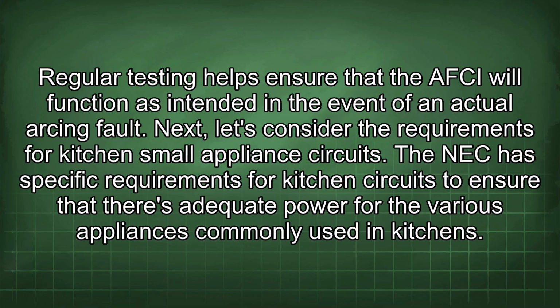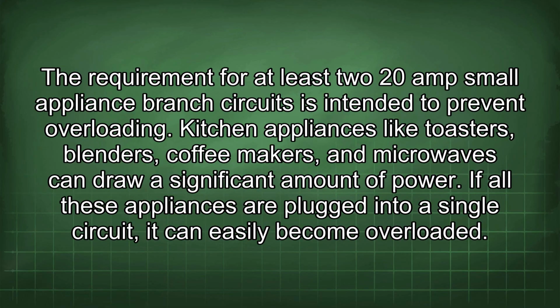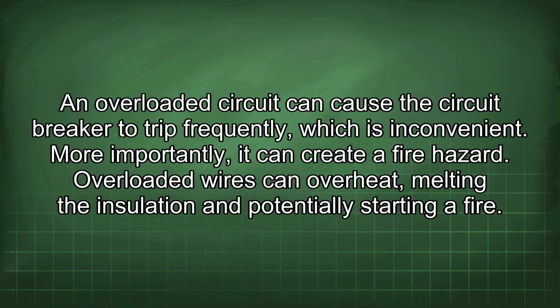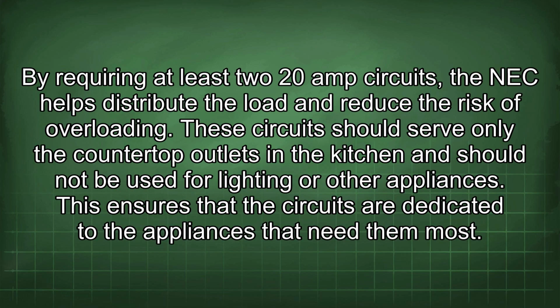Next, let's consider the requirements for kitchen small appliance circuits. The NEC has specific requirements for kitchen circuits to ensure that there's adequate power for the various appliances commonly used in kitchens. The requirement for at least two 20-amp small appliance branch circuits is intended to prevent overloading. Kitchen appliances like toasters, blenders, coffee makers, and microwaves can draw a significant amount of power. If all these appliances are plugged into a single circuit, it can easily become overloaded. An overloaded circuit can cause the circuit breaker to trip frequently, which is inconvenient. More importantly, it can create a fire hazard. Overloaded wires can overheat, melting the insulation and potentially starting a fire. By requiring at least two 20-amp circuits, the NEC helps distribute the load and reduce the risk of overloading.